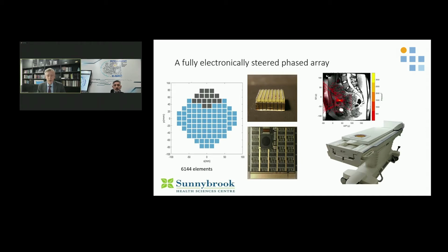And this technology has solved a long-time problem, that we could not have a completely electronically steered phased array. So these are like Lego blocks, and you can build any kind of applicators with these elements. And we have built these blue squares there, where we have 96 of these blocks together, over 6,144 transducer elements, all independently controlled by electronics. So this, of course, provides a system that doesn't have any moving parts. Everything is electronically controlled and provides really fast beam steering.